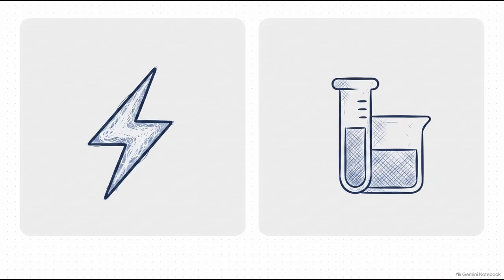It's looking at the water's pH level, its electrical conductivity in microsiemens per centimeter, and its turbidity, which is basically just how cloudy or clear the water is. Why do all this? Well, because even slightly acidic or highly conductive water could cause catastrophic corrosion or electrical shorts right inside the cooling loops.